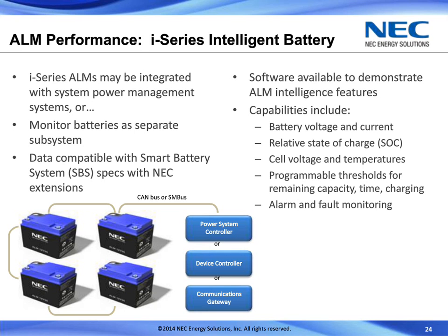We actually have an evaluation demo piece of software that's available for you to plug in and get a view of what these are. But these capabilities include what the current and voltage of the battery is at a given moment, what its current state of charge is, voltages and temperatures at the cell level in the battery. We also provide programmable thresholds for what the remaining capacity and runtime is and charging level of the battery, and also provide some alarm and fault monitoring, so we can trigger when there's some sort of condition that might be of concern to somebody managing a battery system.